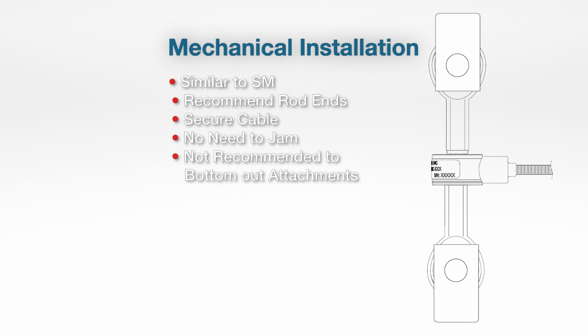Unlike the SM, where you're loading through the flexure itself, with these you're going to be loading through the studs. While it may not be easy to see on that picture, we recommend you don't bottom out the attachment hardware. You don't really need to jam them either. You can. We do have torque values available on that, but they typically perform best if you leave those just a little bit loose, since again you're loading through the studs on these sensors.